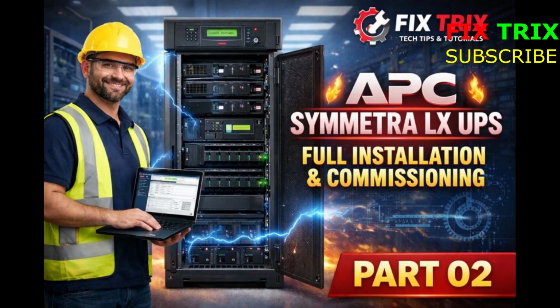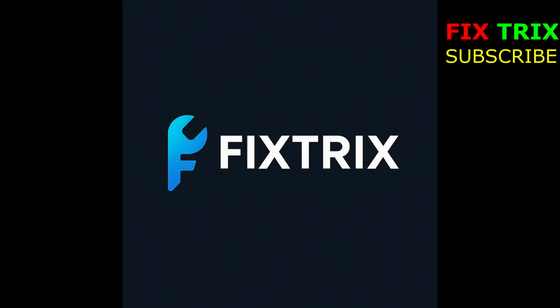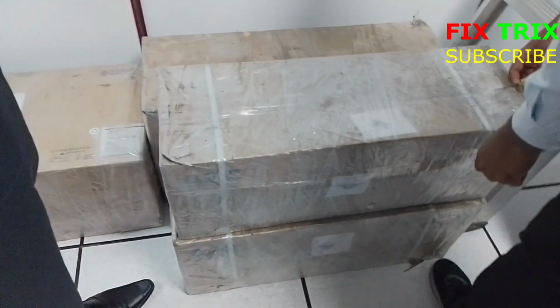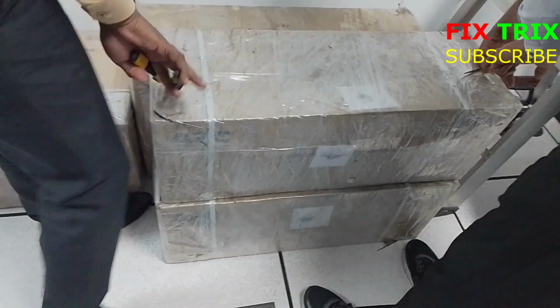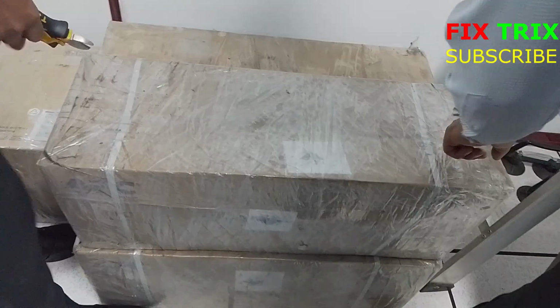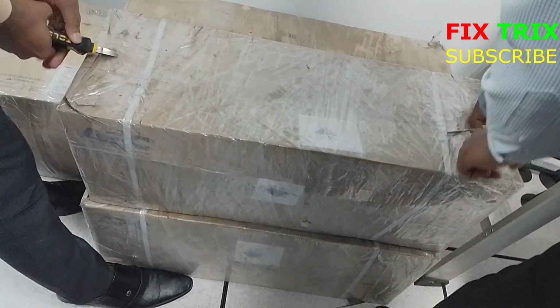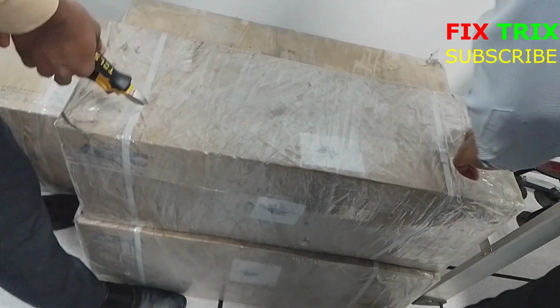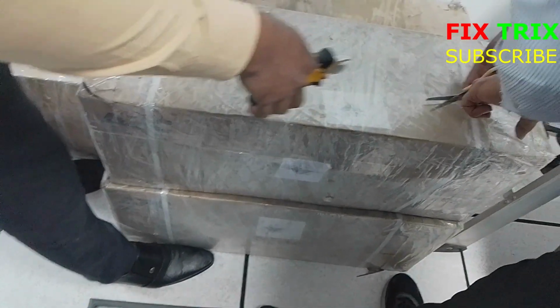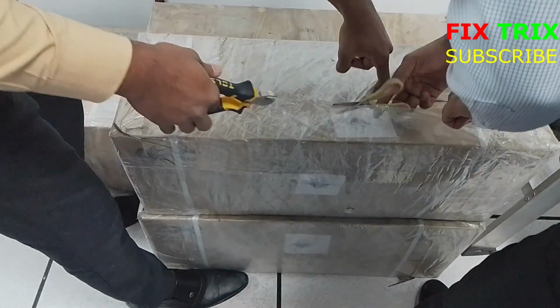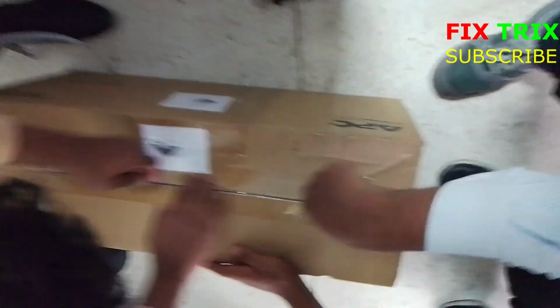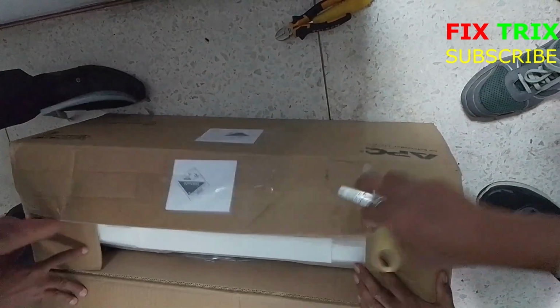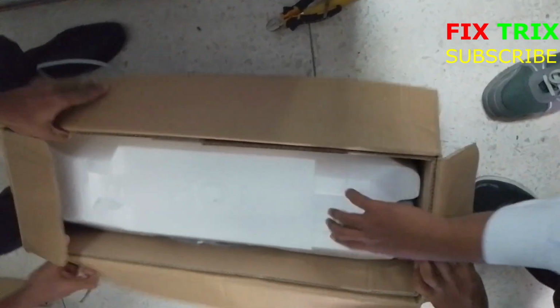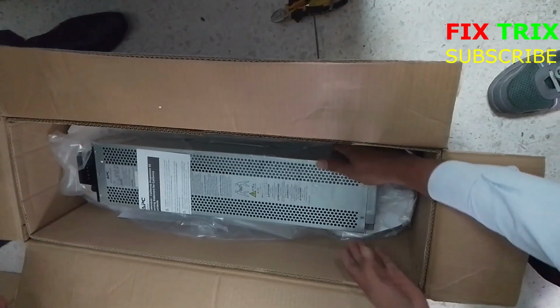This is part 2 of the APC Symmetra LX UPS full installation and commissioning series. Before we continue, please make sure you have watched part 1. In part 1, we explain everything step by step, including APC Symmetra LX UPS overview, unboxing and safety checks, tilt indicator and shipping protection, removing packaging ramps and brackets, safe shutdown of the faulty UPS, input, output and earth connection explanation, removing and installing power and battery module, physical replacement of the UPS. These steps are very important and must be completed before powering on the UPS. Now in part 2, we will continue with commissioning.